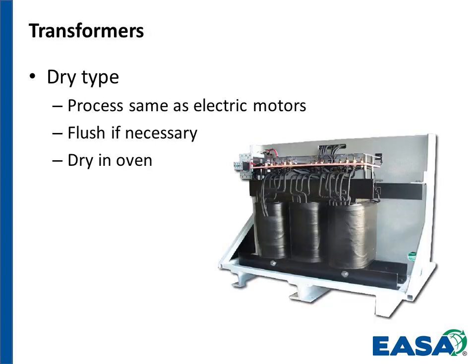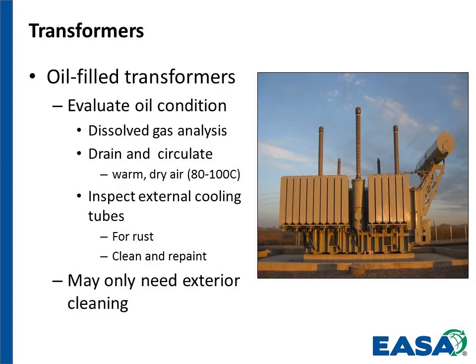Transformers, another big issue. Not as big an issue as you might think at first blush. The dry type transformers, as we see here, the process is just like for the electric motors. The windings are exposed. If they've been immersed, then they'll need to be flushed in the same manner and cleaned and then dried out.